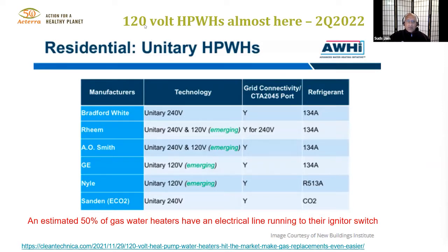Now there are these 120 volt heat pump water heaters that are almost here, available in a few months, with different manufacturers making these. Rheem, for example, will have a 240 volt and a 120 volt version. The 120 volt doesn't have that resistive heating backup, so if you had this in a really cold garage, it may not work unless it's designed to operate down to colder temperatures, like 20 degrees. You'd have to be careful using one of these in a garage that gets really cold.